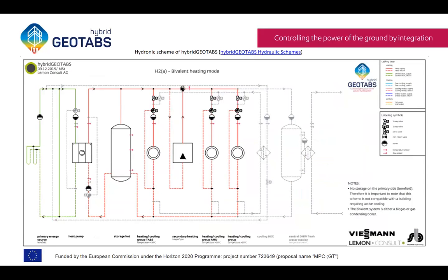Two issues you should be aware of, not problems, but issues: domestic hot water with higher temperature levels, which is also integrated in some schemes. How do you solve that? And secondly, the regeneration of the ground. If you don't have a balance, because your building doesn't have a comparable heating and cooling demand over a year, then you could use other solutions like solar thermal panels to regenerate, or a cooling tower to regenerate your borehole field in a very efficient and environmentally friendly way.